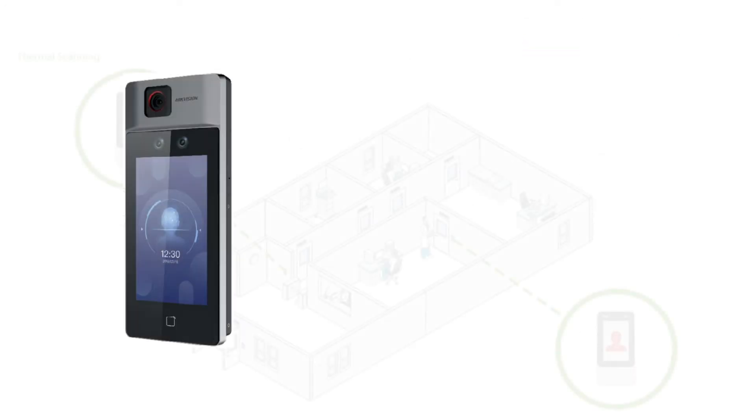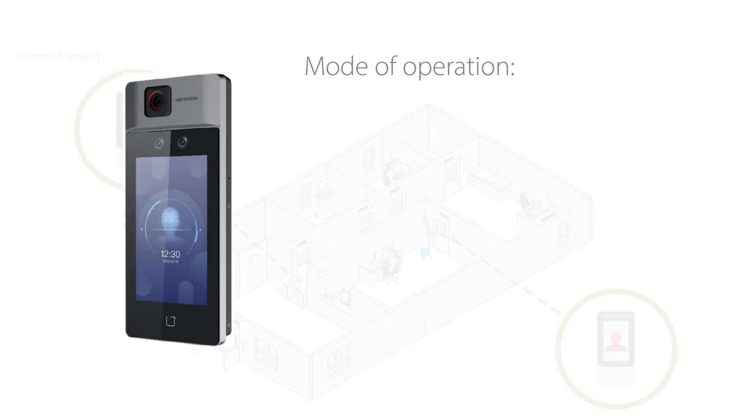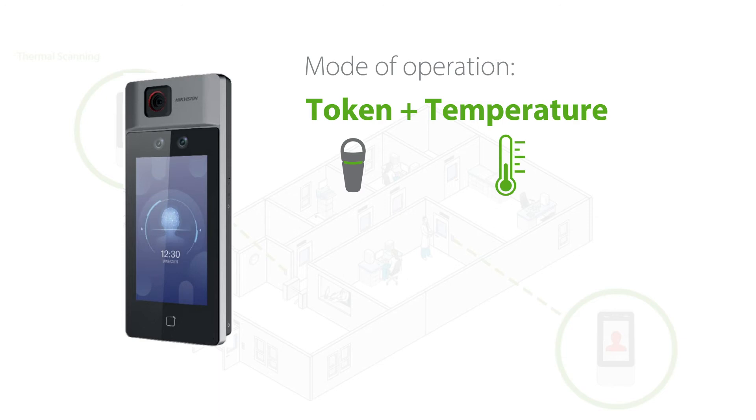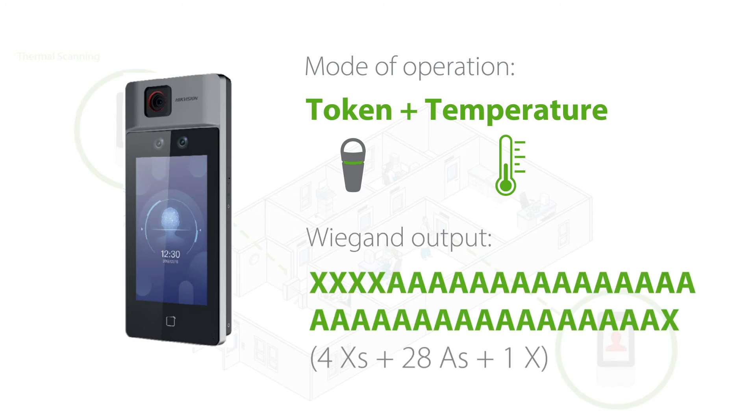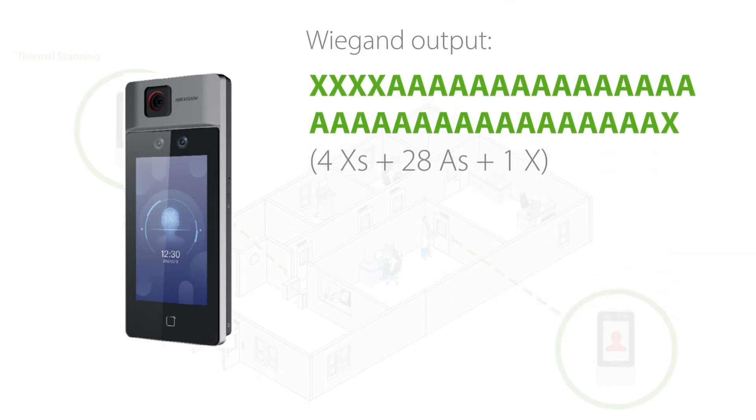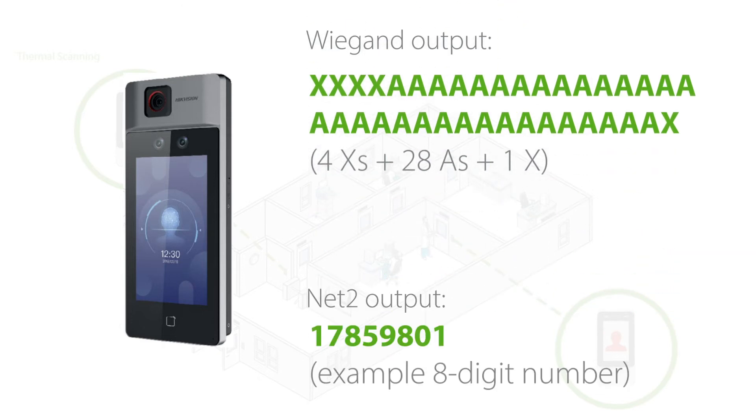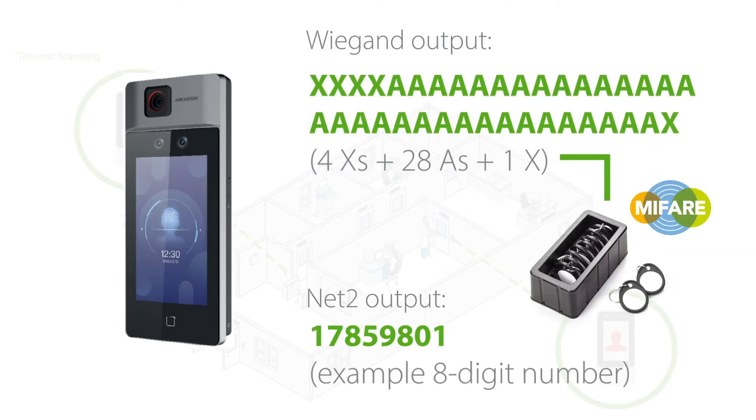Ensure that the manufacturer's instructions are followed when installing the thermal scanner into the environment. In this example, the unit's mode of operation should be configured to token plus temperature and output a Wiegand format. Hikvision and Dahua readers can output the Wiegand number in the NET2 token format when using a Mifare token, allowing the same card to be used across the site.